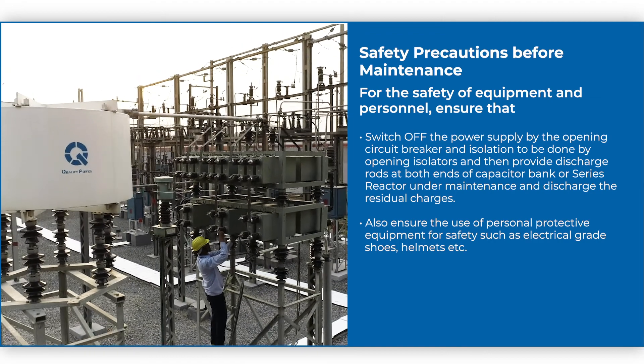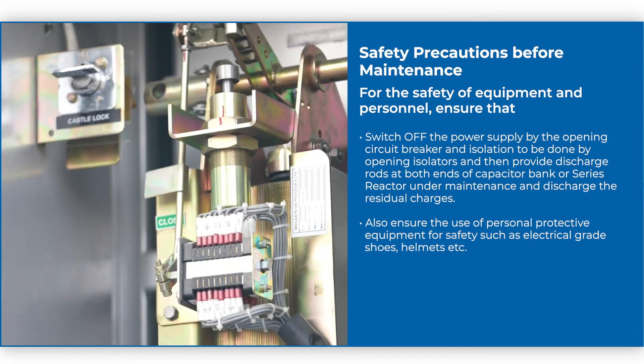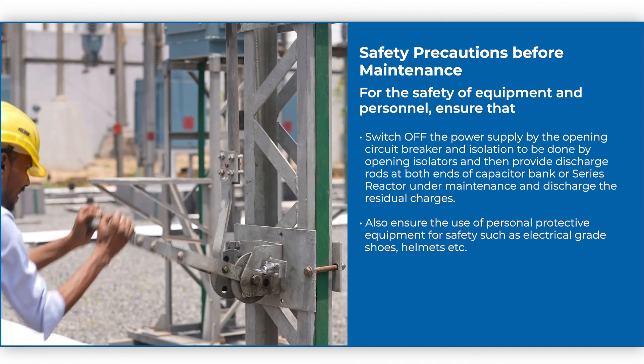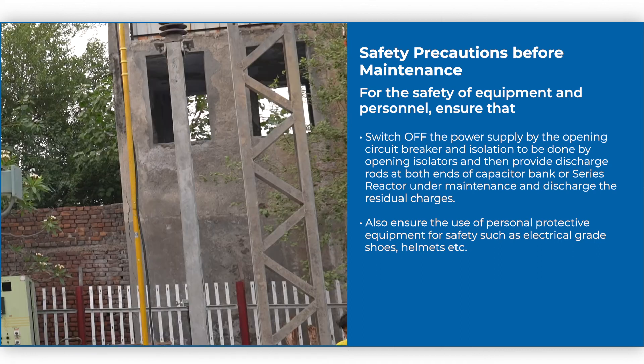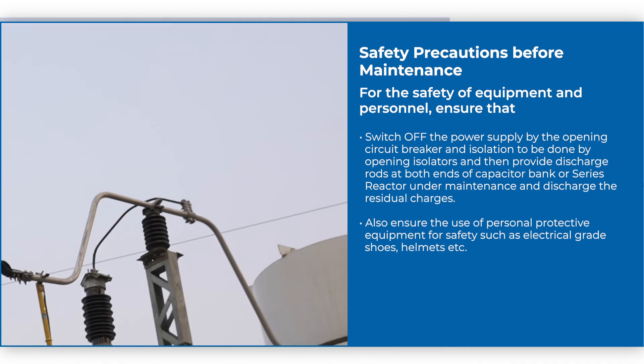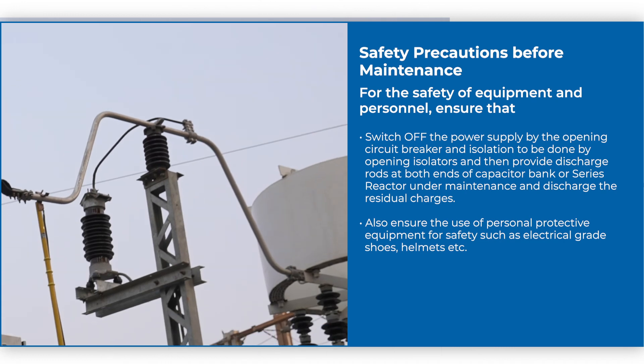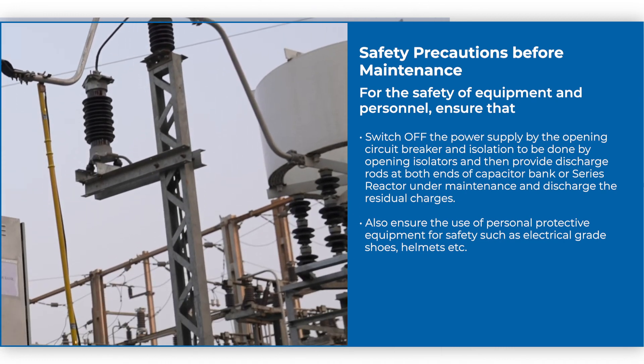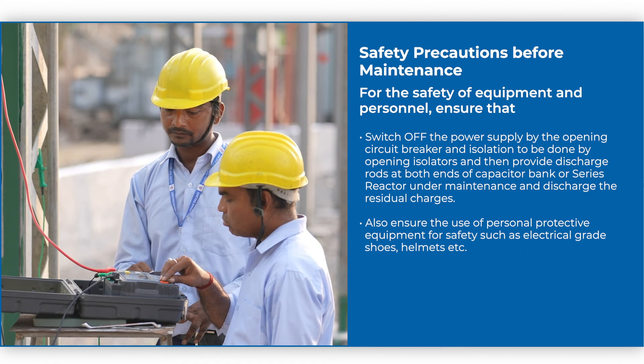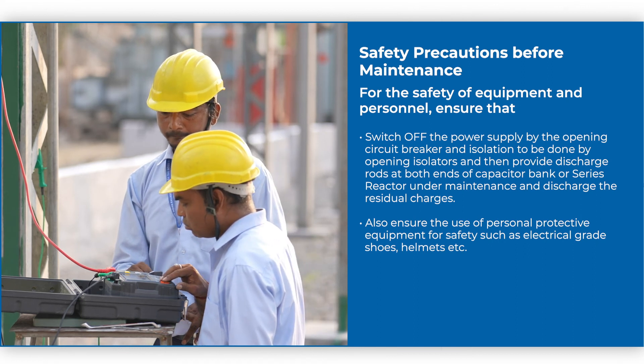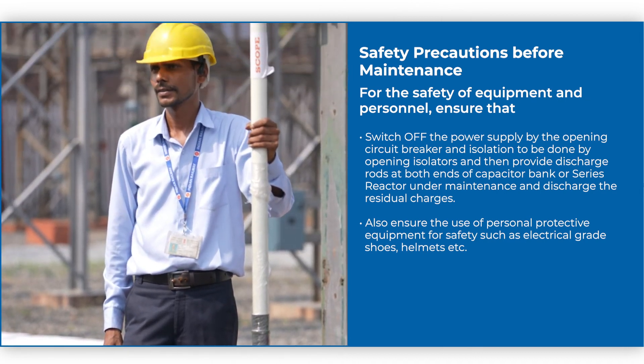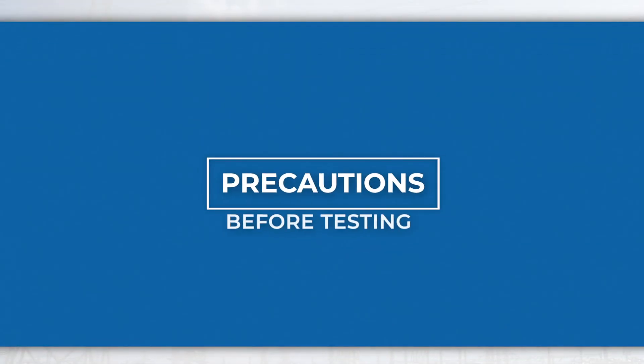Safety precautions before maintenance: for the safety of equipment and personnel, ensure that the power supply is switched off by opening the circuit breaker. Isolation shall be done by opening the isolators, and then provide discharge rods at both ends of the capacitor bank or series reactor under maintenance and discharge the residual charges.